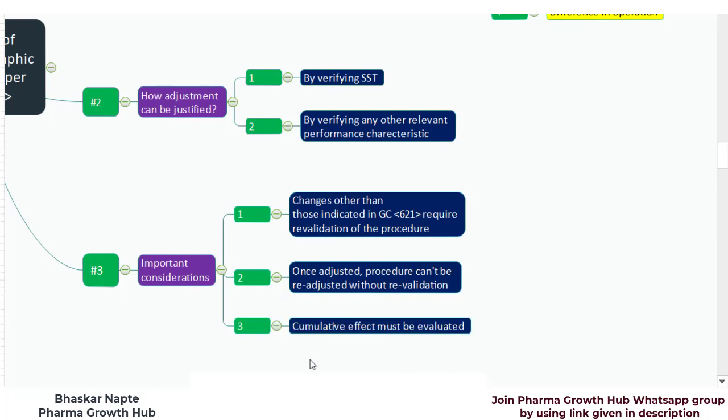The cumulative effect must be evaluated. If you are trying to change multiple parameters — parameters belonging to the column, parameters belonging to the mobile phase, and parameters belonging to injection volume — all of these changes together can contribute, possibly negatively, to your relevant performance characteristics. So you must understand the influence of contributing changes because of the cumulative effect you are trying to bring in.